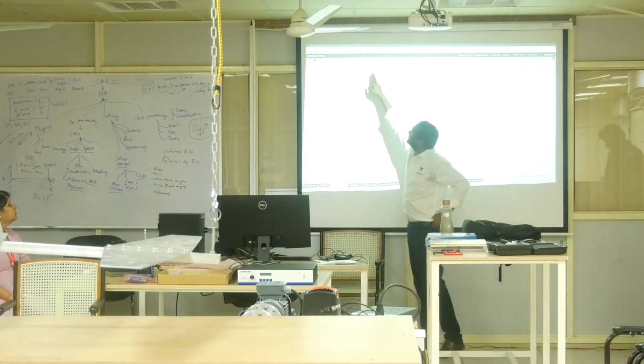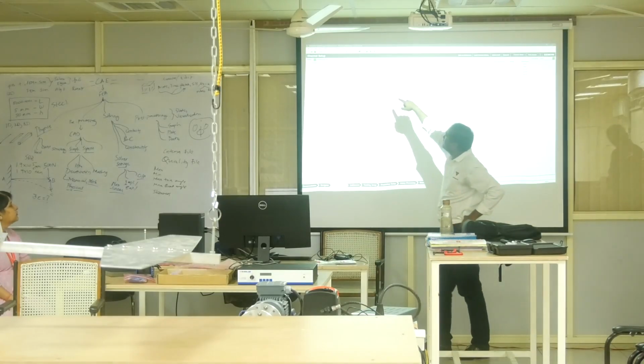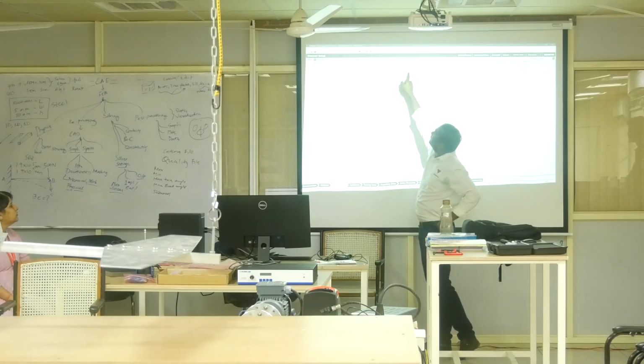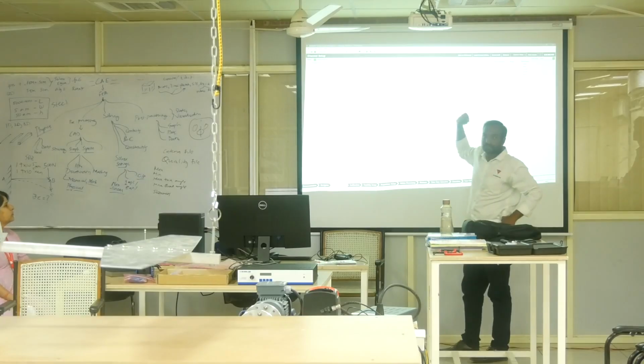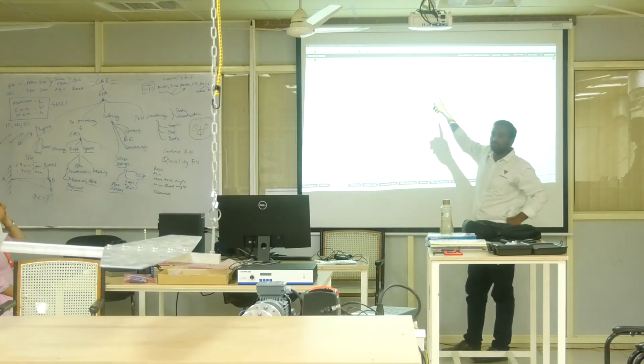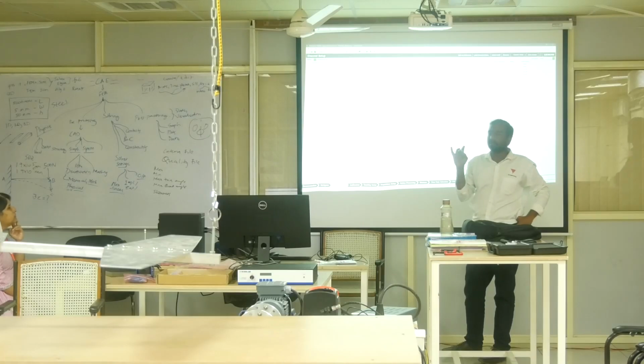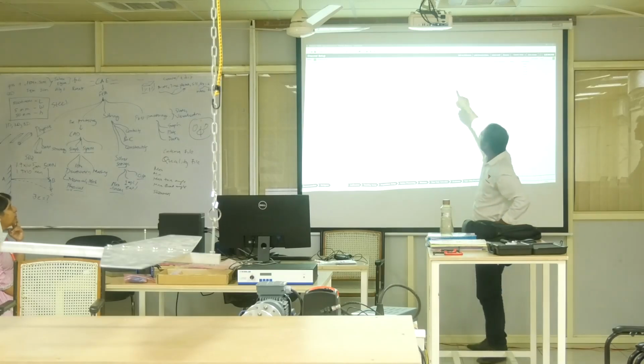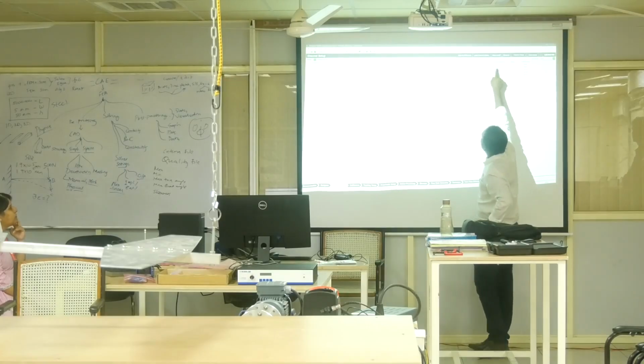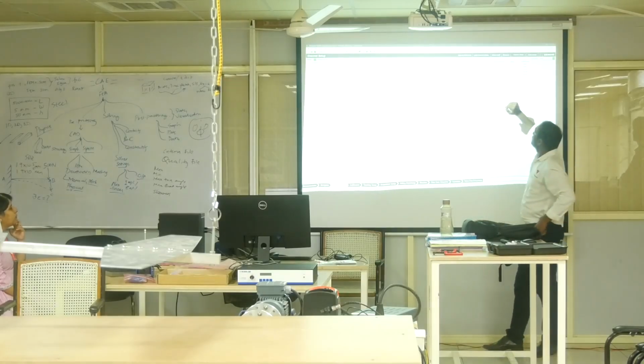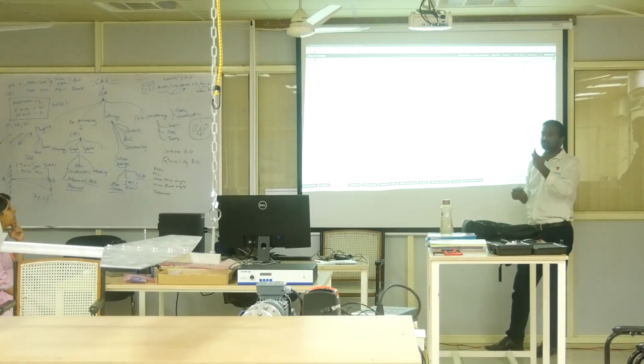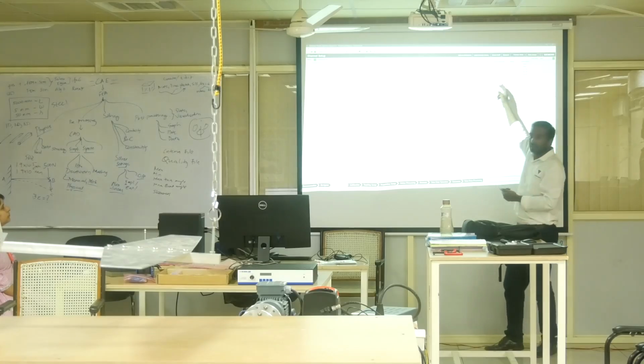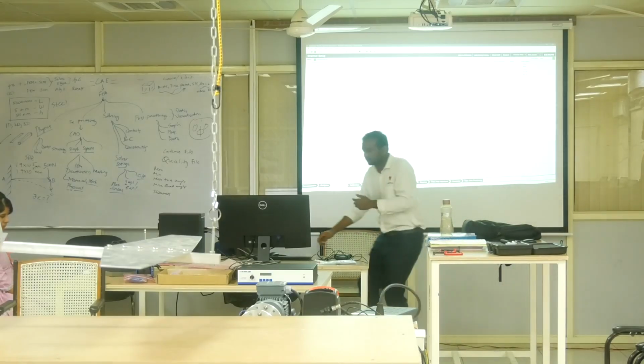I can set the axis, which is x, y, z written over here. Next we can set the quantity that we want to measure. Here it's measured as acceleration. Vibrations can be measured in 3 forms: acceleration, velocity and displacement. And we can set the calibration values, which are nominal sensitivities. There are actual sensitivities and nominal sensitivities, which can be set according to the documentation provided by the calibration or the manufacturer itself. Once we set that and the axis, we can go for the next worksheet.